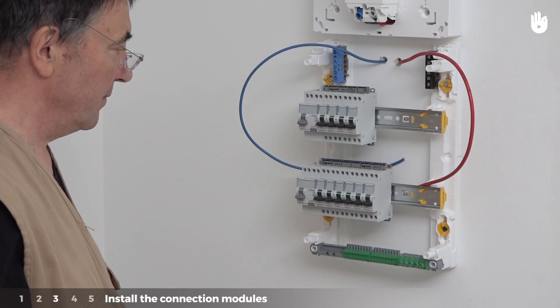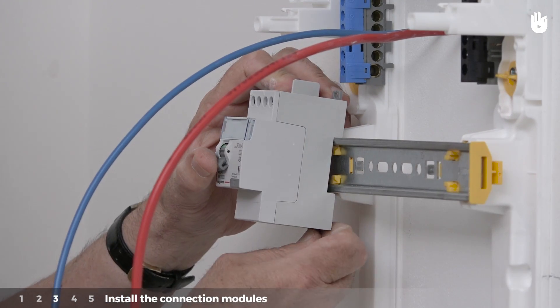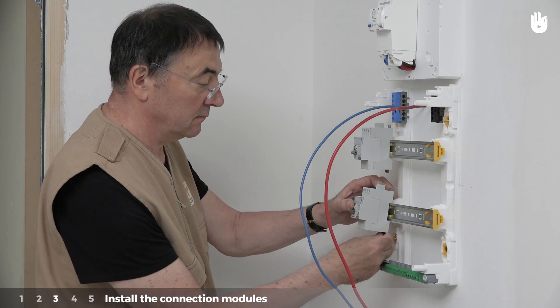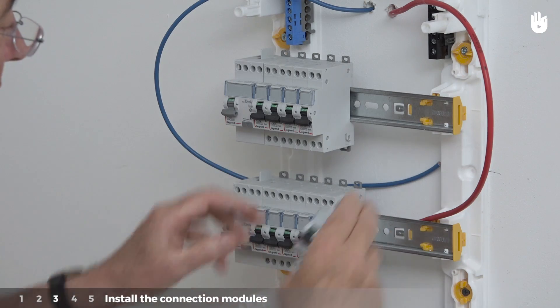Step 3. Install the connection modules. The circuit breakers clip onto the rail. At the beginning of each row, attach the 30mA residual current circuit breaker. Then install the individual circuit breakers in order of decreasing load.